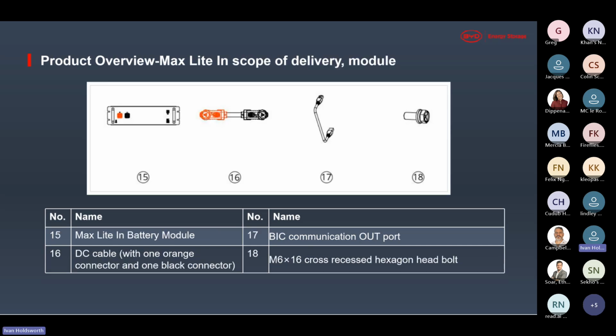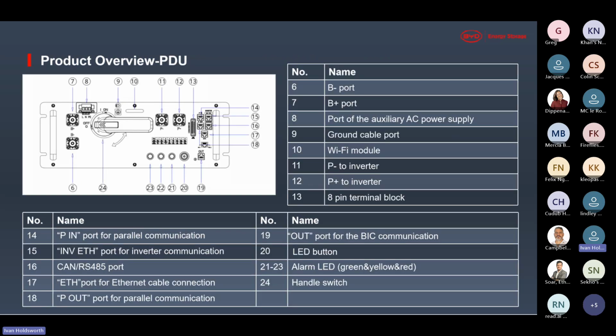And this is what you get in the box. You get your module, a cable to daisy chain your power to the next module, your communications cable, and your mounting brackets. Very briefly, you can go through the PDU.